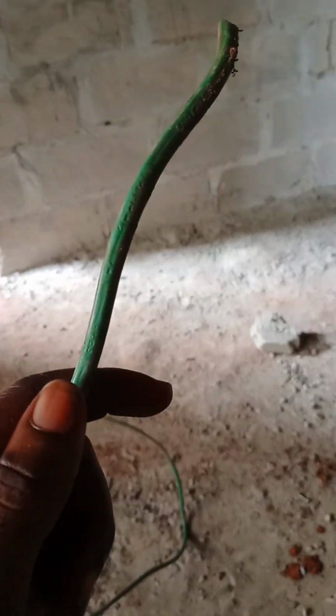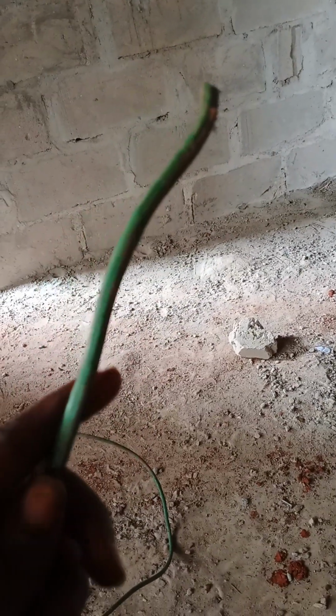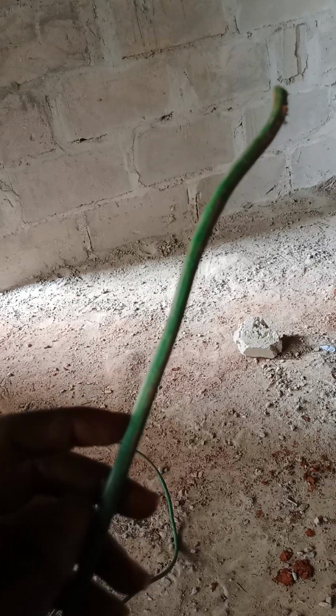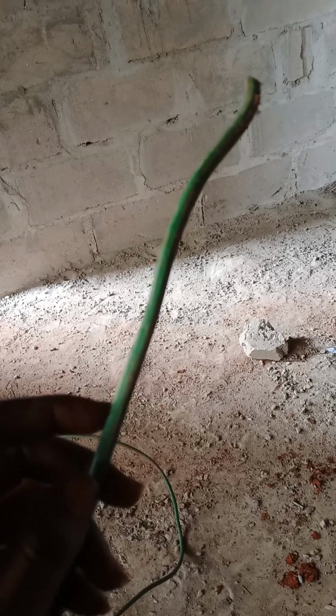When you are considering doing earthing in a building, you have to also consider the cable size. The cable size is important because when you have a short circuit, the current actually increases. So the cable size that will arrest those short circuit faults and leakage current faults to the general mass of the earth needs to be considered, and you need to use copper cable.